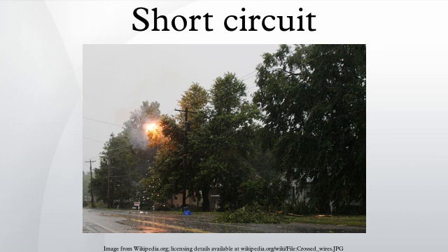Possible effects include unexpected energization of a circuit presumed to be isolated. To help reduce the negative effects of short circuits, power distribution transformers are deliberately designed to have a certain amount of leakage reactance. The leakage reactance helps limit both the magnitude and rate of rise of the fault current.